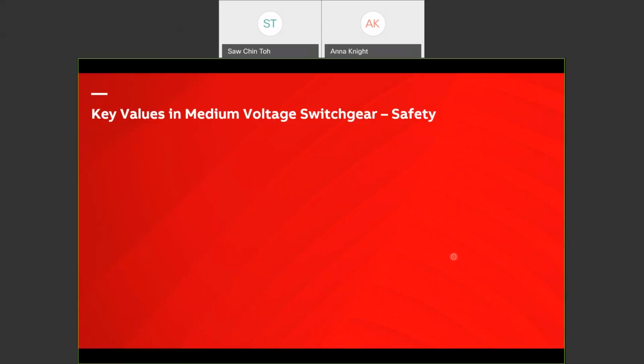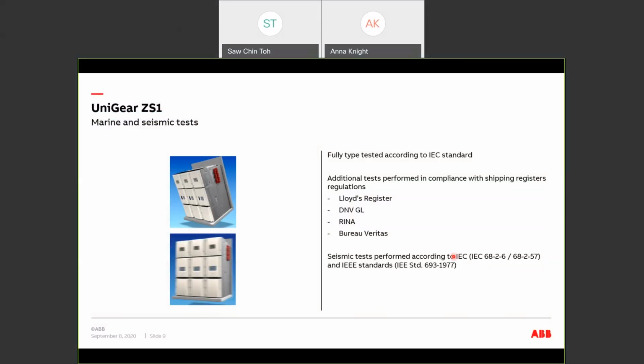UniGear panels have considered many safety features in design. First of all, we will fulfill all the type tests according to the IEC standards. On top of that, we also perform additional tests, for example, the inclination test and the vibration test, to cover the compliance for the major shipping registers, for example, Lloyd's Register, DNV-GL, RINA, and Bureau Veritas. Seismic tests are also carried out on the panels according to the IEC and IEEE standards.